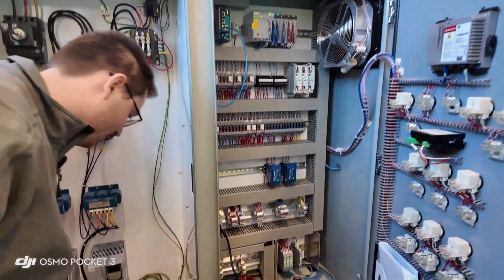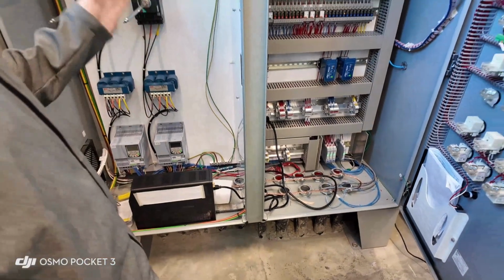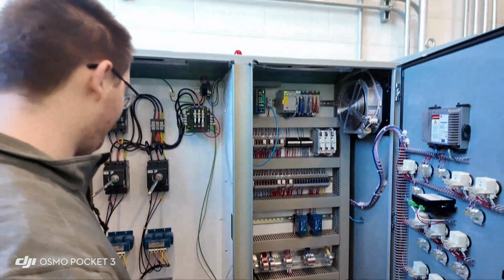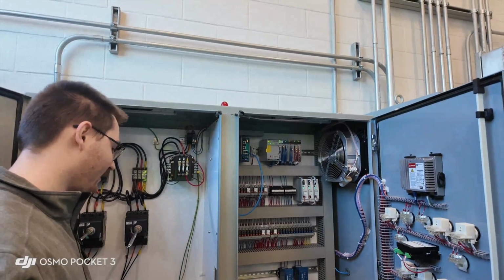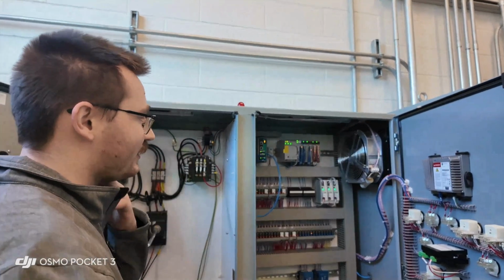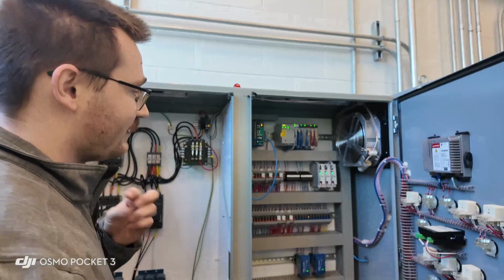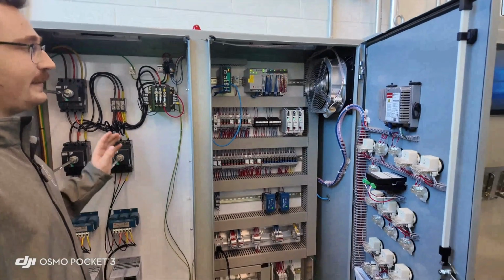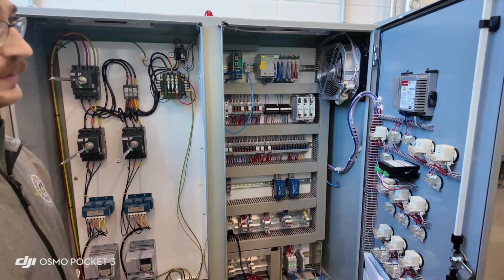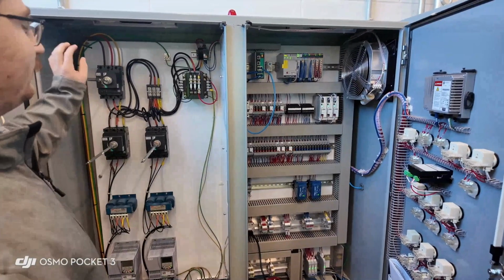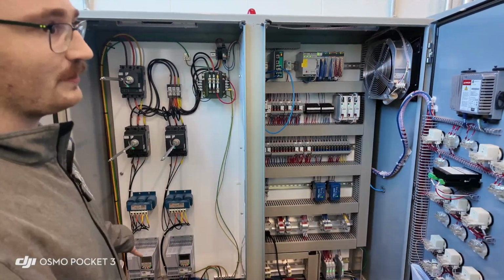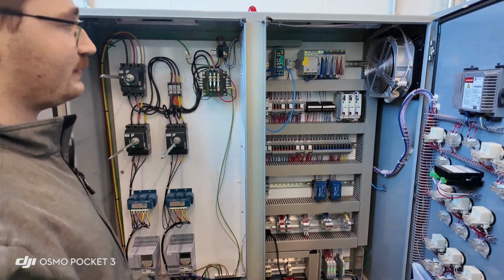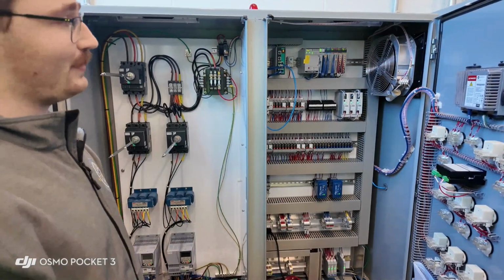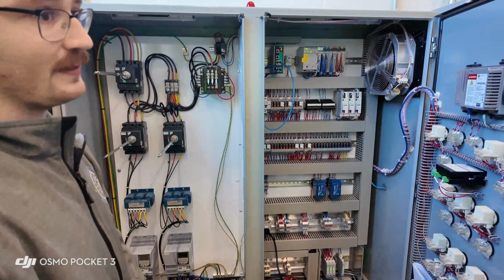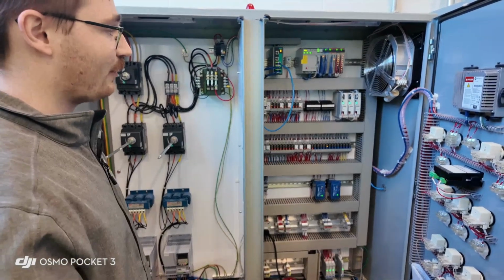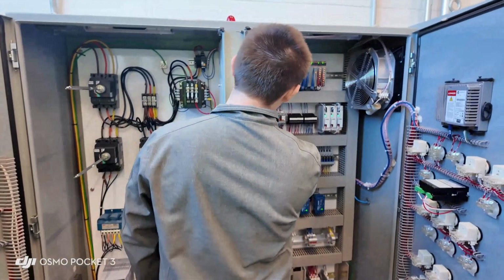This is backup UPS. If there's ever a control panel power fail, it will run to UPS backup power, and it will run the PLC. It's pretty much, I think, estimated runtime is about 25 to 30 minutes, but it's pretty much just going to be used for alarming. If you do have a power fail, it means you've lost your main breaker, so you're not really going to be able to operate any pumps anyways. It'll just allow the PLC to send out every alarm it has pretty much over to SCADA, and it'll warn you, say, hey, you have a power fail. That's coming from this BMR relay.